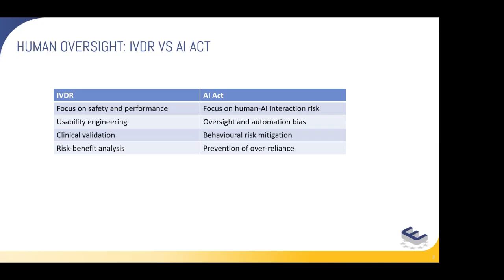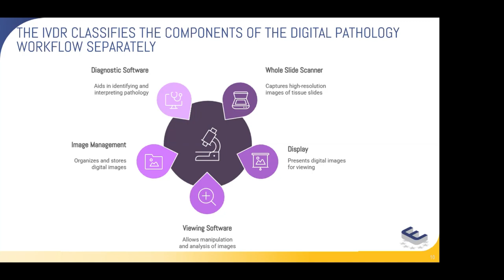Unlike the US, the IVDR breaks down digital pathology systems into their individual component parts. So you've got your whole slide scanners, you've got your display, you've got your viewing software, you've got your image management tools, and then you may have some additional diagnostic software on top of that. Where the US sees this as a whole system, the IVDR allows manufacturers to classify these in a modular approach, and so each of these is classified separately. So what this means is that each of these individual components could fall under a different risk class depending on the intended purpose and the impact of incorrect results in the context of the intended purpose.